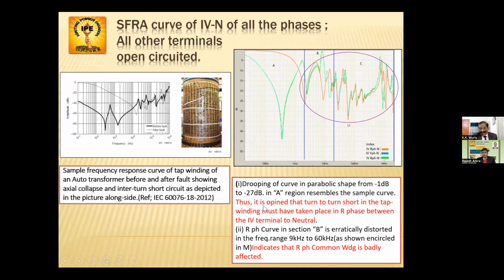Okay. So this tap winding comes into picture. So thus it is opined that turn-to-turn short in the tap winding must have taken place in R phase between IV terminal to neutral. R phase curve in section B. This is the section B. R phase curve in section B is erratically distorted in the frequency range 9 kilohertz to 60 kilohertz. See, this is 9 kilohertz. Okay, 9 kilohertz to 60 kilohertz. 60 kilohertz here. And the 100 kilohertz is here. As shown encircled in M. This is M encircled, ellipse. Indicates that R phase common winding is badly affected.